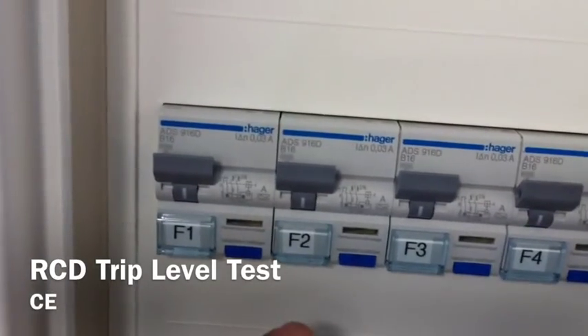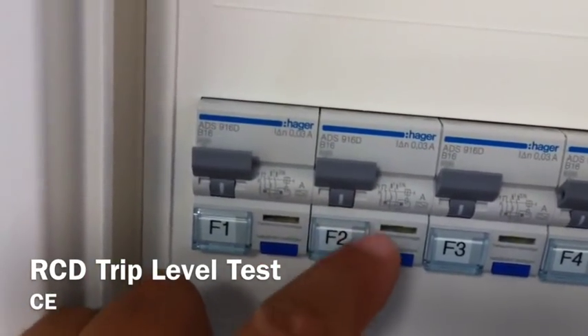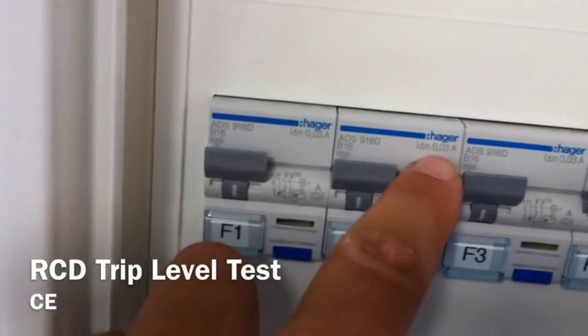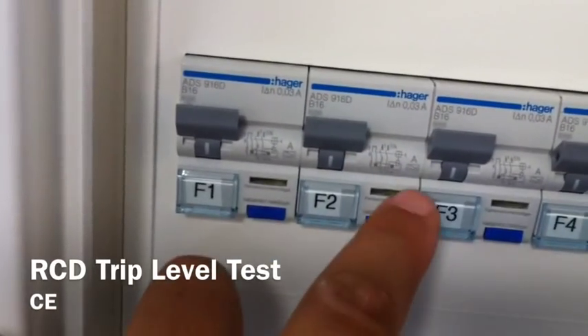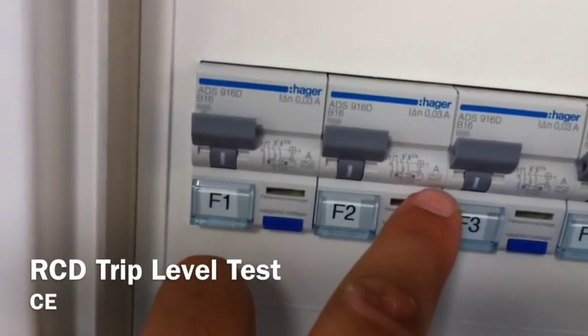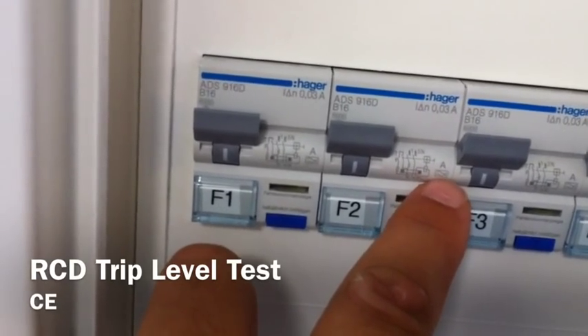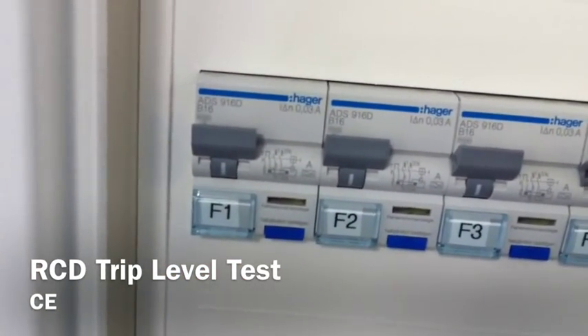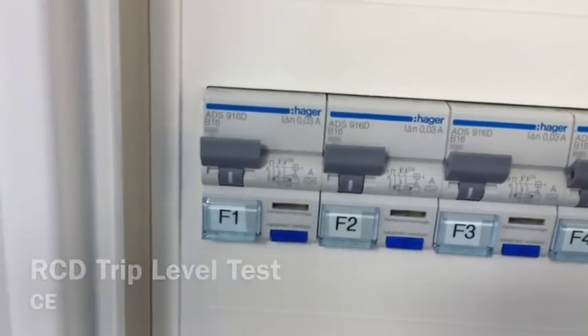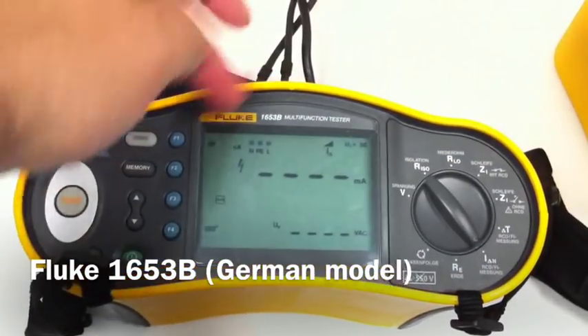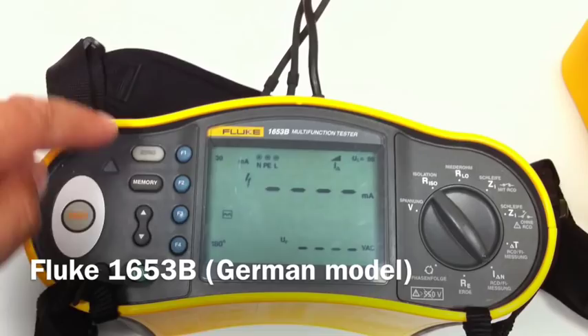We have an RCD here, an RCBO from Hager. It has a trip current of 30 milliamp and it's a type A - here's the symbol for it, an AC with a pulsing current detection. The meter is set up with the appropriate leads according to what is shown on our display.